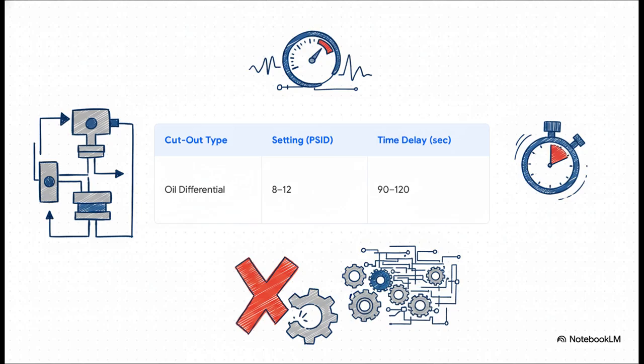You can see it right there in the table. There's the pressure setting itself, a really tight window of 8 to 12 psid. But look at that other column, the time delay. The system is engineered to ignore a quick, normal little dip in pressure, but if the problem sticks around for more than 90 seconds, it shuts everything down. It's just a brilliant piece of preventative design.